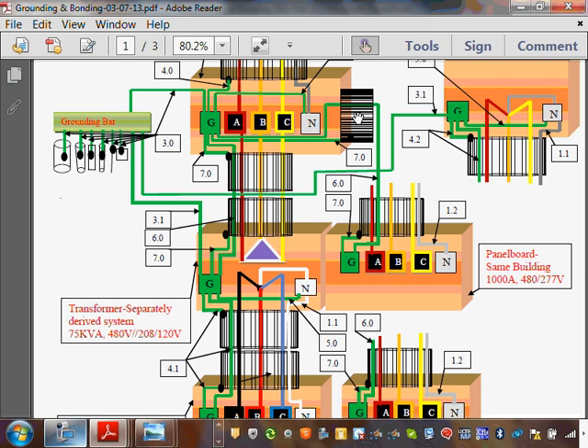So that's where it becomes bonding the equipment depending on the voltage. Now, if your voltage is 208/120 or 240/120, you can. That's why you see it sometimes, because 208/120 is 3-phase, and 240/120 is single phase or 3-phase, it doesn't matter down at the equipment level. The only time they become strict on it is if your system voltage is 480/277 because of arcing. Okay, makes sense?